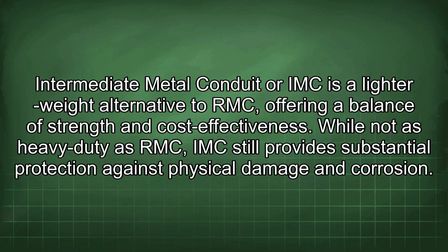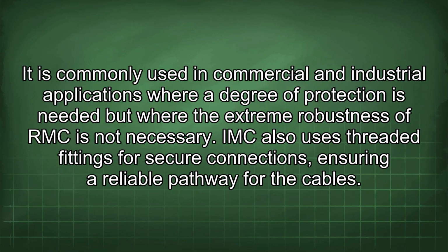Intermediate metal conduit or IMC is a lighter weight alternative to RMC, offering a balance of strength and cost-effectiveness. While not as heavy-duty as RMC, IMC still provides substantial protection against physical damage and corrosion. It is commonly used in commercial and industrial applications where a degree of protection is needed but where the extreme robustness of RMC is not necessary. IMC also uses threaded fittings for secure connections, ensuring a reliable pathway for the cables.